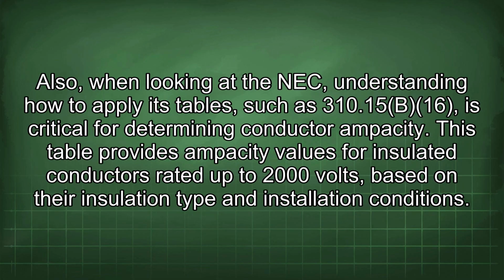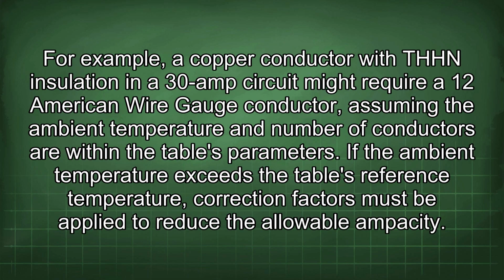Also, when looking at the NEC, understanding how to apply its tables, such as 310.15(B)(16), is critical for determining conductor ampacity. This table provides ampacity values for insulated conductors rated up to 2000 volts based on their insulation type and installation conditions. For example, a copper conductor with THHN insulation in a 30 amp circuit might require a 12 American wire gauge conductor, assuming the ambient temperature and number of conductors are within the table's parameters.